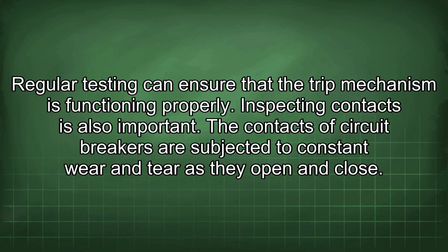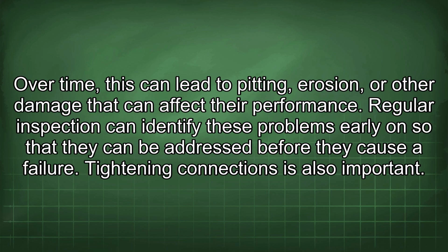Inspecting contacts is also important. The contacts of circuit breakers are subjected to constant wear and tear as they open and close. Over time, this can lead to pitting, erosion, or other damage that can affect their performance. Regular inspection can identify these problems early on so that they can be addressed before they cause a failure.